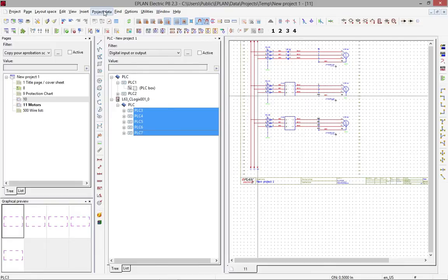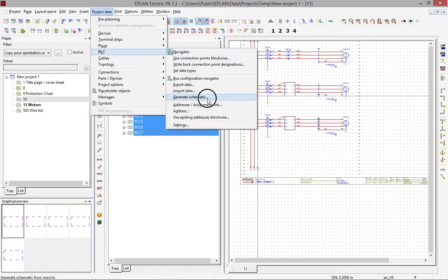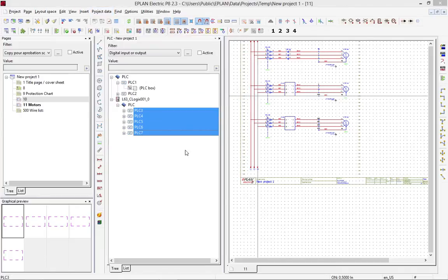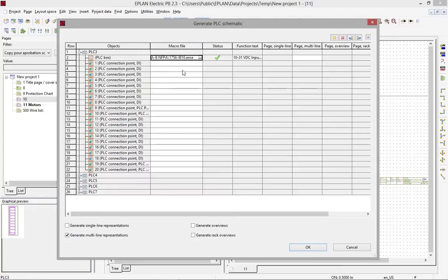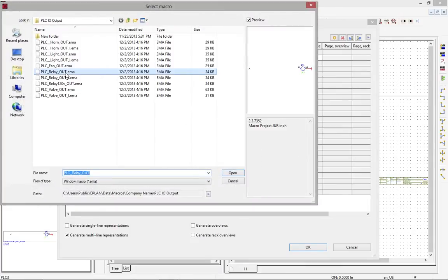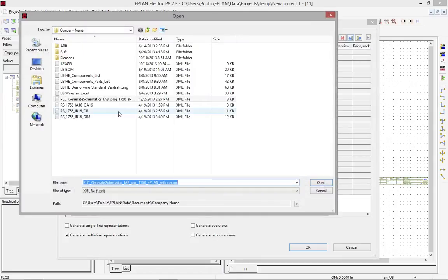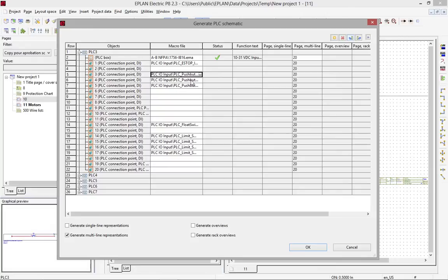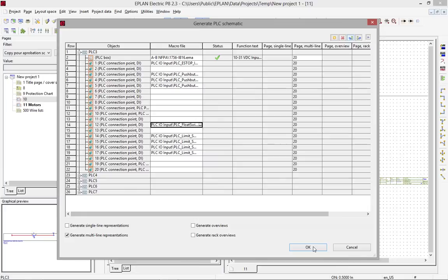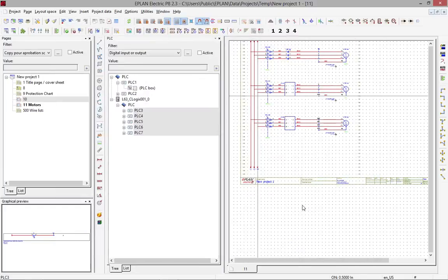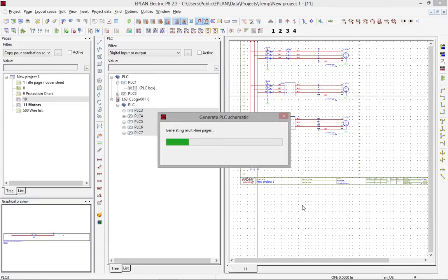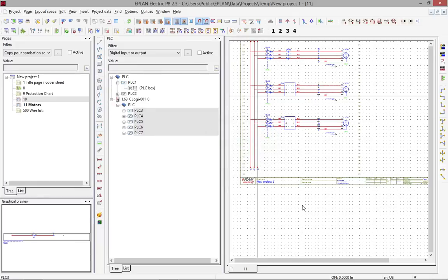Now what I can do is I can generate the PLC pages that correspond to these PLC cards. Automatically, ePlan recognizes the part number, and I can actually associate each of these inputs and outputs with a small macro. I created a standard here which automatically assigns a few push buttons, limit switches, and flow switches to my inputs and output cards. I can just simply click OK, and this will generate for these five PLC cards the PLC pages for each individual I/O card.